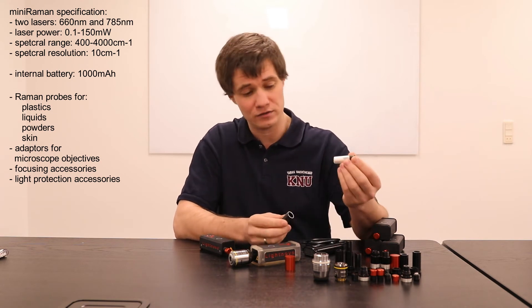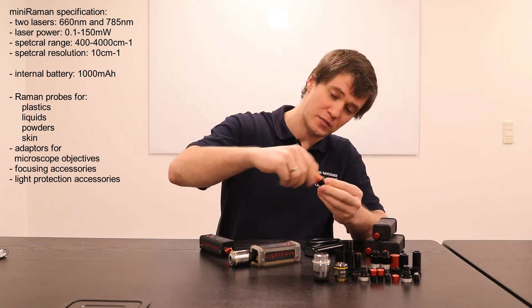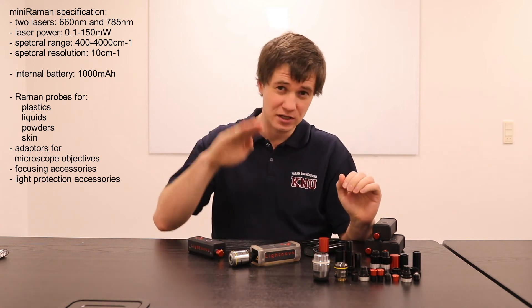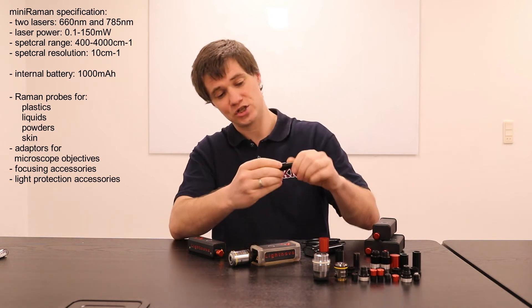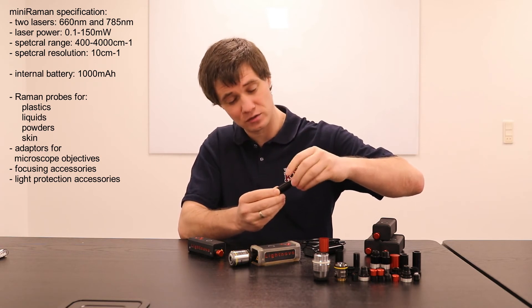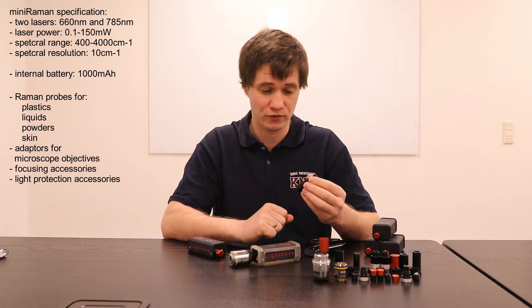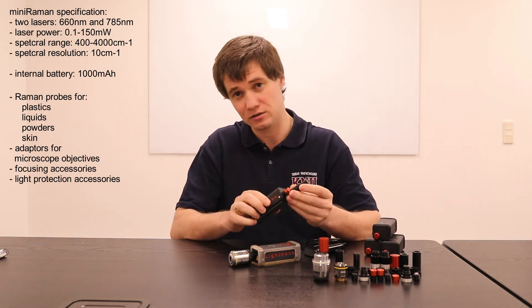For example, if you have a vial with powder or liquid, you can insert it here, then protect it with a cover and attach it to the spectrometer for measurements. If some fine focusing adjustment is needed, we have an accessory which allows you to tune the focusing position of your sample with regard to the focal point where the laser spot should be focused, so you can maximize signal and then start doing measurements.